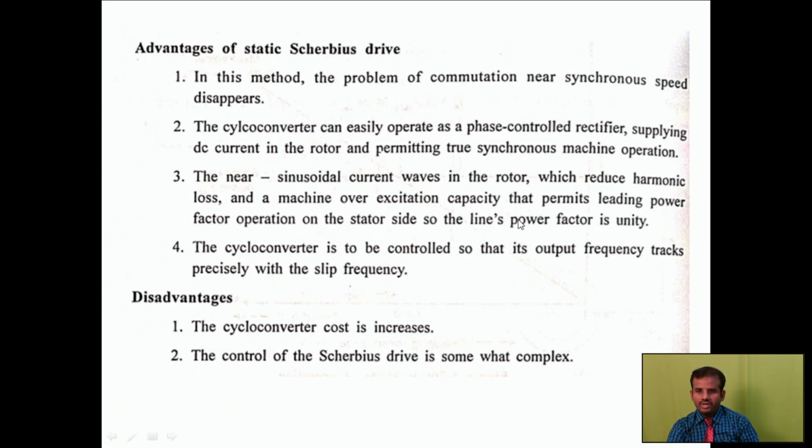So if it is leading power factor operation on the stator side, the line's power factor is unity in this method. The cycloconverter is to be controlled so that its output frequency tracks the slip frequency. This is the advantage of static Scherbius based drive. The disadvantage is that the cycloconverter cost increases, and the control of the Scherbius based drive is somewhat complex. We have to use more SCRs in the cycloconverter, so the converter cost is very high, and the control circuit is also very complex.